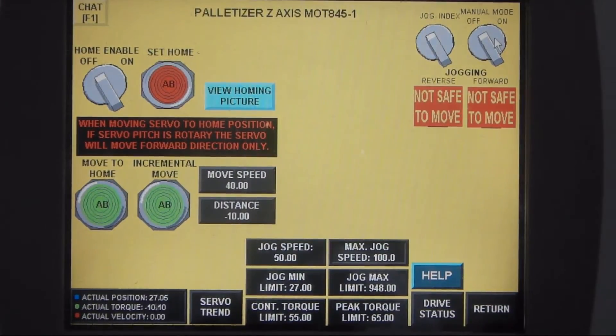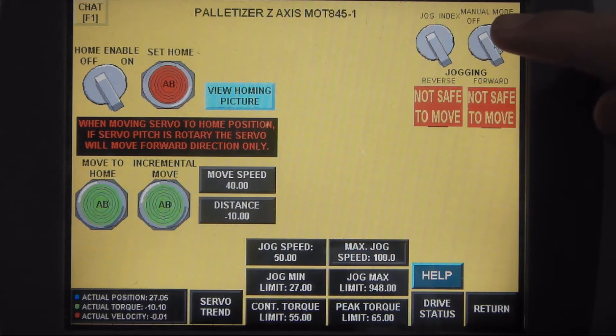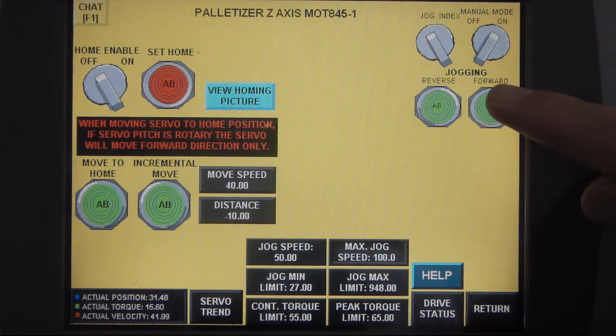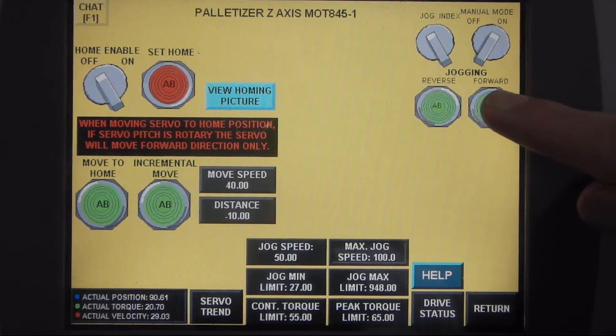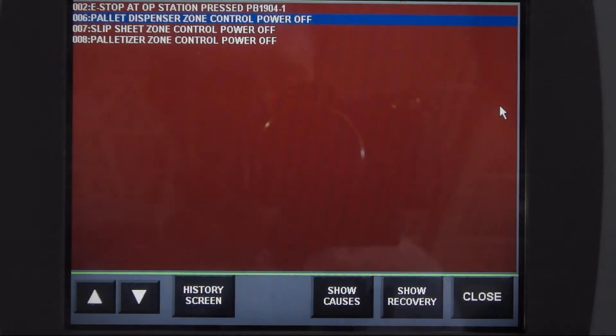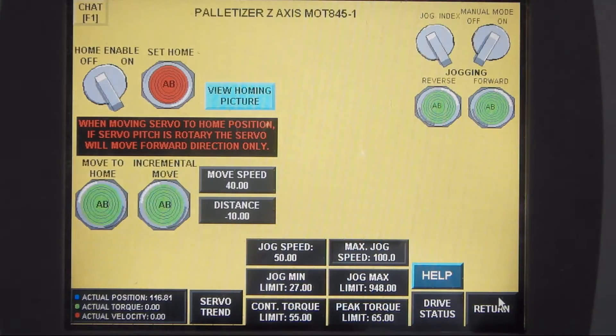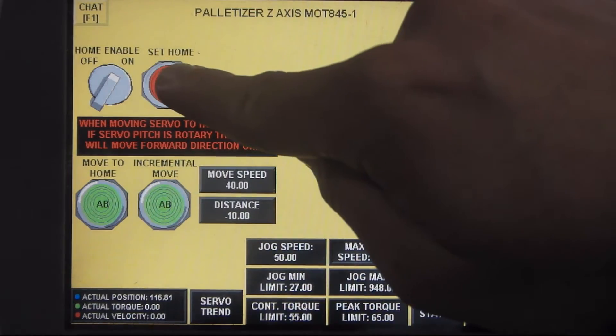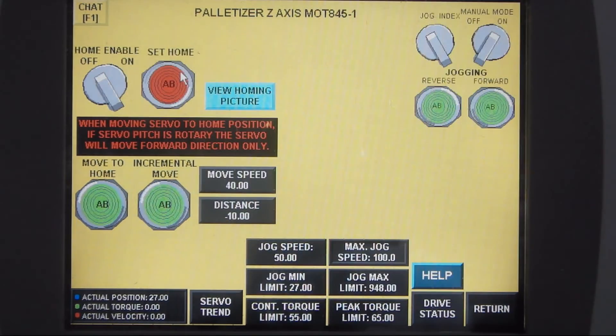So if the marker is off, you have to re-home the servo back to the correct position. First we turn manual mode on, and then you have to jog the Z axis. You can jog it here to the home orange position marker as indicated. So now you e-stop the machine, turn home enable on, and then you click set home. And now you'll see that go off, so now you're back into the home position.